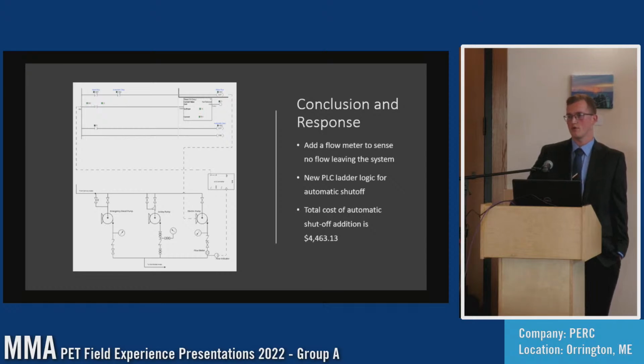I talked with both the superintendent of the plant and the safety manager and decided that 15 minutes was a suitable time, as we don't want the pump automatically turning off as soon as a line is closed, because they might have to use it right again. The total cost of adding the new system in, which involves a flow meter, would be about $4,463. This is already half the price of the shaft itself, let alone the seals and the possibility of repetitiveness. That's all.